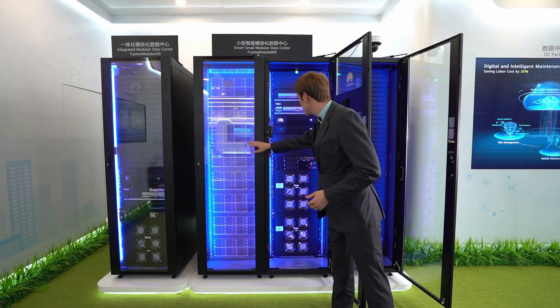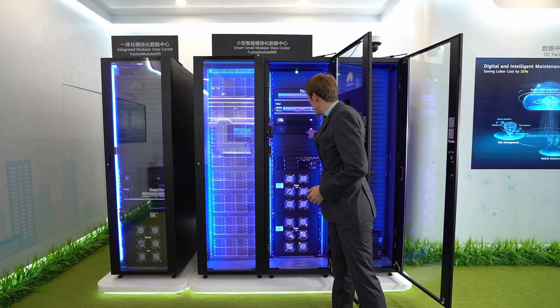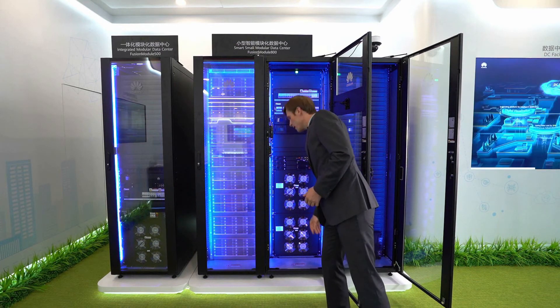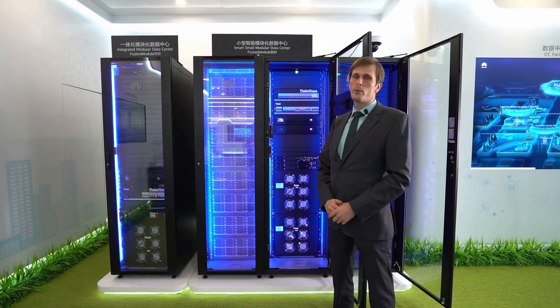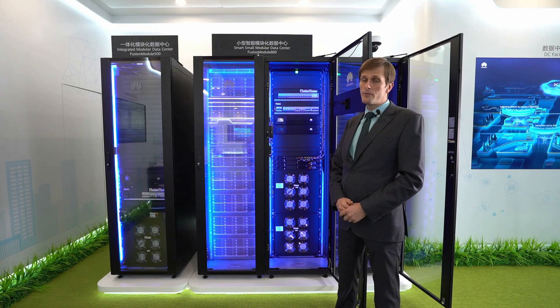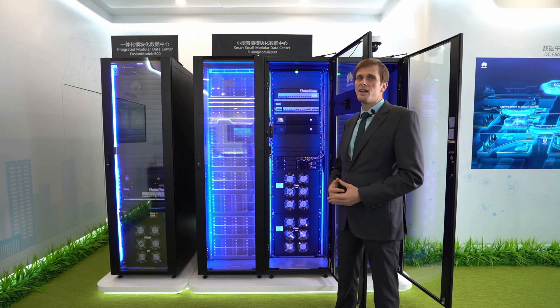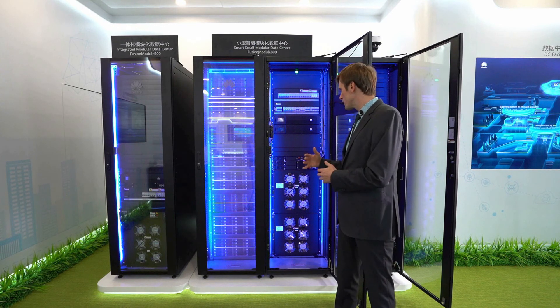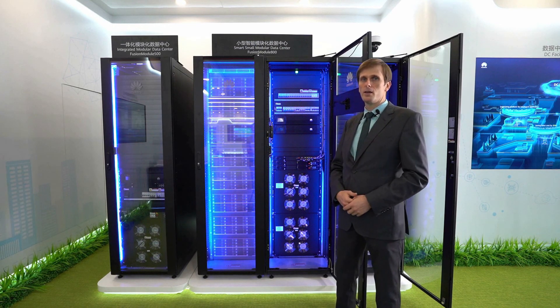You can close this. There is a redundant UPS, there is a redundant ECC board for management, and there is a redundant air conditioner. So any component is redundant. If we have any problems inside, the system can still work and we have enough time for an engineer to come and fix the faulty part.